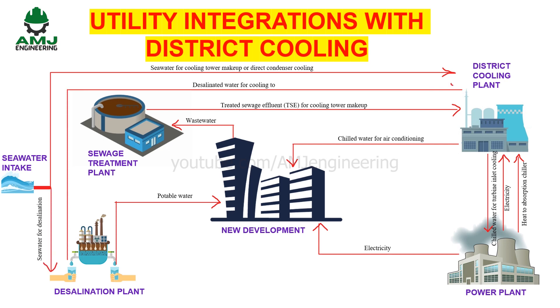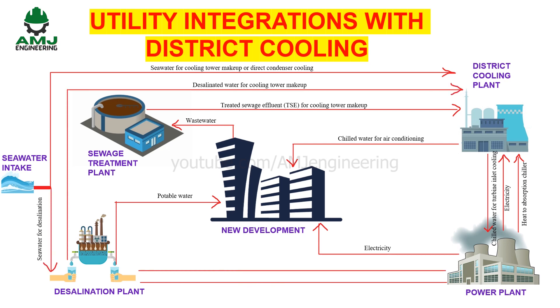Another makeup water source could be from desalination plants like RO plants. The salinity of product water from an RO plant can vary significantly depending on the salinity of the feedwater and the specific type of RO process employed. In general, the cost of RO decreases as the minimum acceptable product water salinity increases. For this reason, it is much more attractive to desalinate brackish water or treated sewage effluent than it is to desalinate seawater.